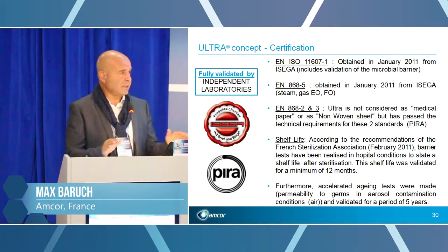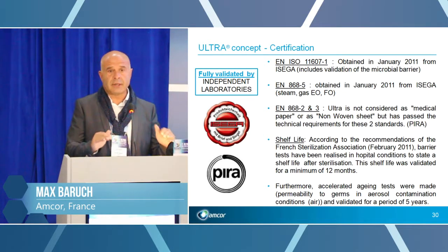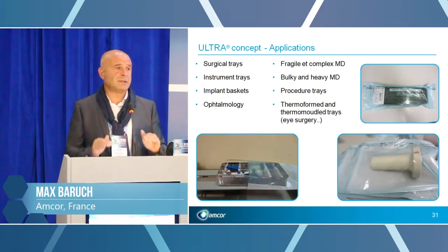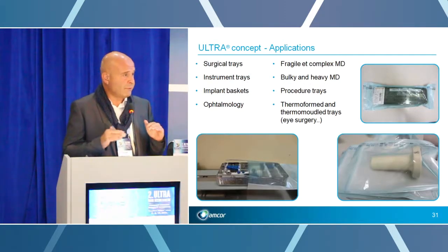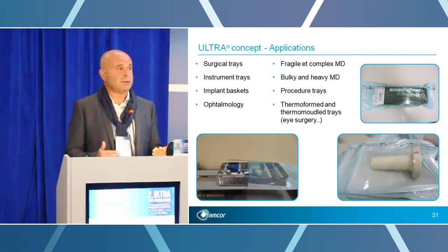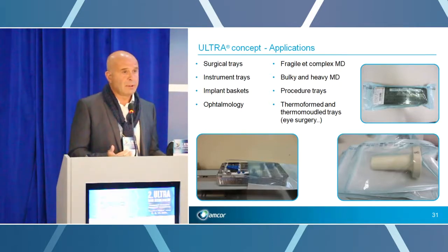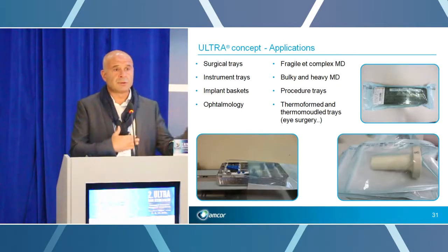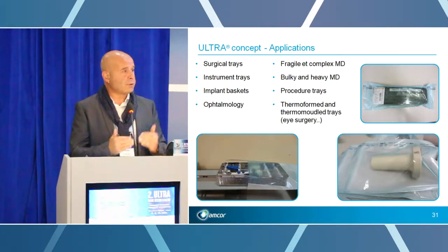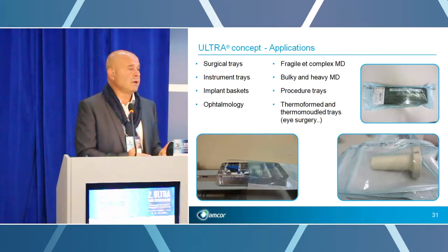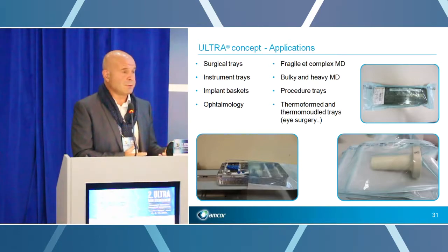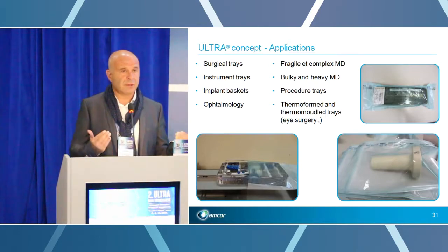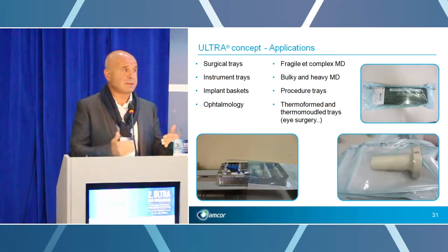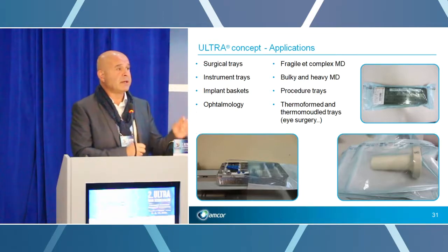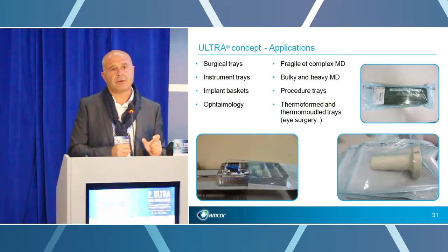The standard doesn't say to use single or double. It just says you decide in function of the risk in your CSSD. If you have a very important risk during transportation and storage, you do double. If you don't have any risk because you use a strong material and you have good storage and good conditions of transportation, it's possible to use a single packaging, because the SBS, the sterile barrier system, is the minimum packaging for the medical device. Okay?